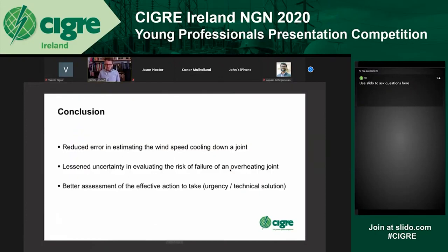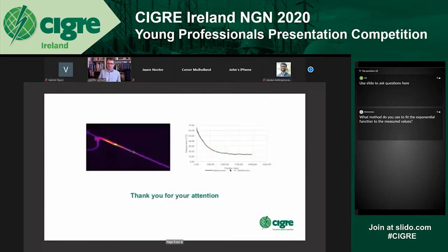To conclude, I showed you a new method to reduce the error in estimating the wind speed cooling down a joint, and it can help lessen the level of uncertainty when you evaluate the risk of failure of an overheating joint, which means we have a better assessment of the effective action to take with that joint, either the urgency to act or the technical solution you should choose. I thank you for your attention.